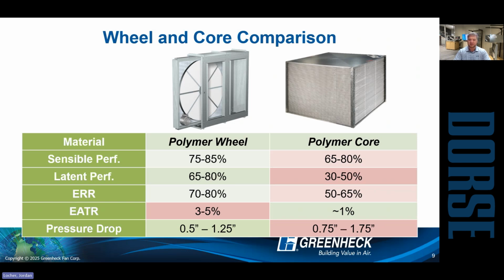Last one I'll say is just general sizing, right? So in the smaller airflow ranges, if you're under 1500 CFM, it's more of a pick your flavor. When you get to higher CFM, you're pushing 2, 3, 5, 10,000 CFM, the advantages of the wheel really start to become greater and greater, and the sizes of those cores start to grow significantly.